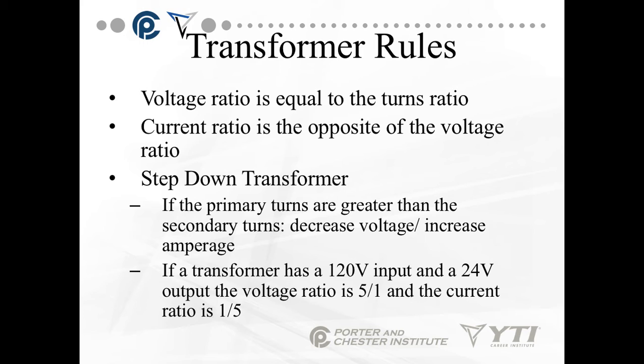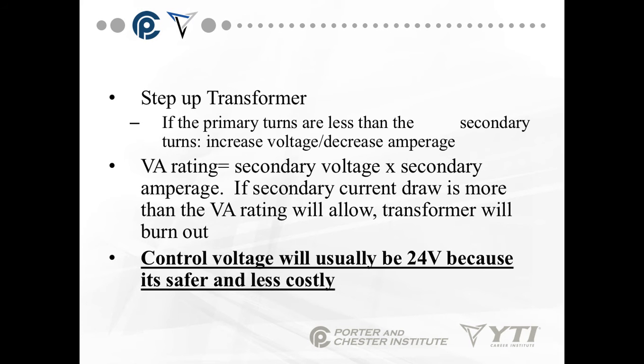So a step-down transformer says that if the primary turns are greater than the secondary turns, the voltage will decrease and the amperage will increase. Okay? So a step-down transformer decreases the voltage but increases the amperage. So if a transformer is 120 volt input and a 24 volt output, the voltage ratio is 5 to 1, but the current ratio is 1 to 5. A step-up transformer says that if the primary turns are less than the secondary turns, the voltage will increase, but the current will decrease. For air conditioning, most often you're going to use a step-down transformer. Where we see step-up transformers is with oil and gas ignition in the heating side of things.